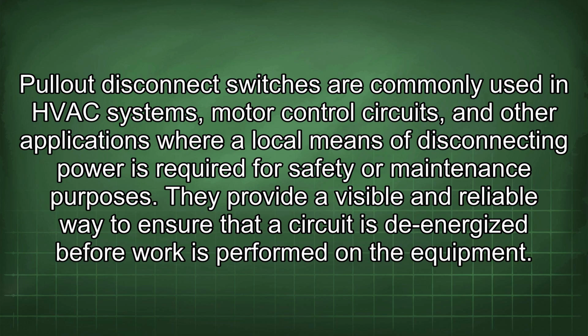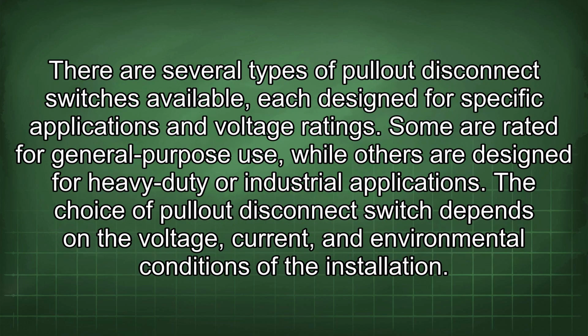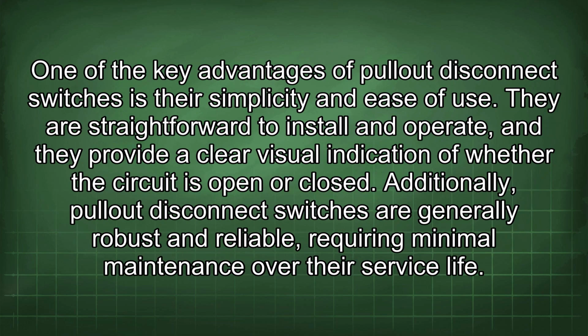They provide a visible and reliable way to ensure that a circuit is de-energized before work is performed on the equipment. There are several types of pullout disconnect switches available, each designed for specific applications and voltage ratings. Some are rated for general purpose use, while others are designed for heavy-duty or industrial applications. The choice of pullout disconnect switch depends on the voltage, current, and environmental conditions of the installation. One of the key advantages of pullout disconnect switches is their simplicity and ease of use. They are straightforward to install and operate, and they provide a clear visual indication of whether the circuit is open or closed. Additionally, pullout disconnect switches are generally robust and reliable, requiring minimal maintenance over their service life.